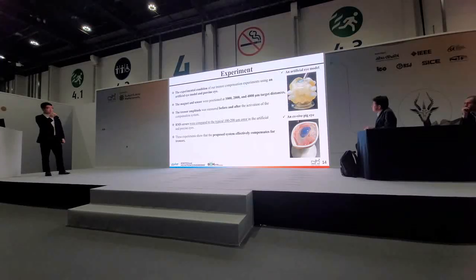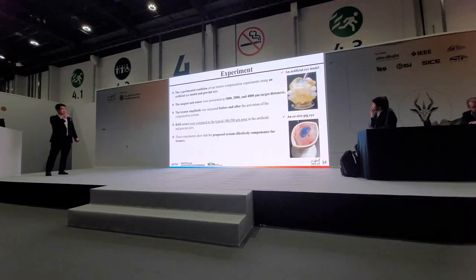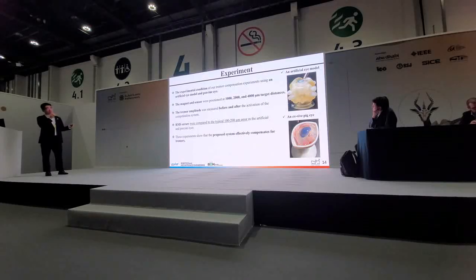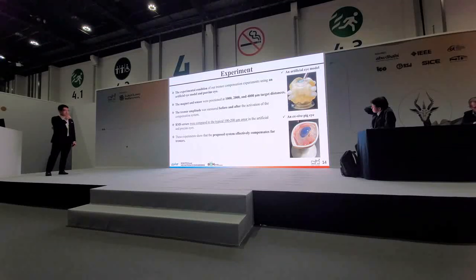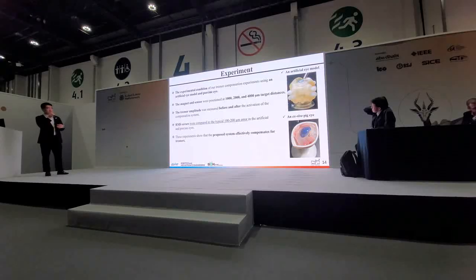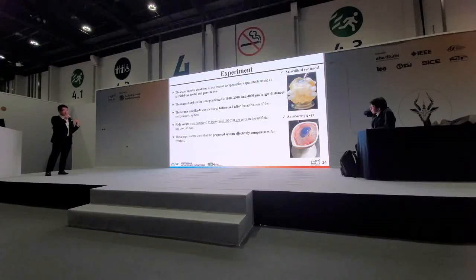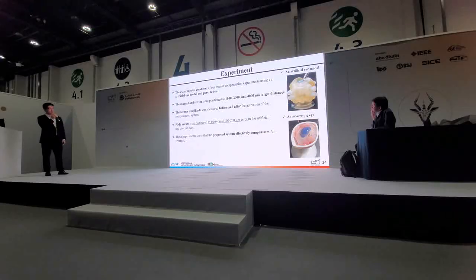Let's move on to experiment part. The condition of our tremor compensation experiment using an artificial eye model and porcine eye. The magnet and sensor were positioned at 1,000, 2,000, and 4,000 micrometer target distance. The tremor amplitude was measured before and after the activation of the compensation system. RMS errors were compared to the typical error 100 to 200 micrometers in artificial and porcine eyes. These experiments show that the proposed system effectively compensates for tremors.